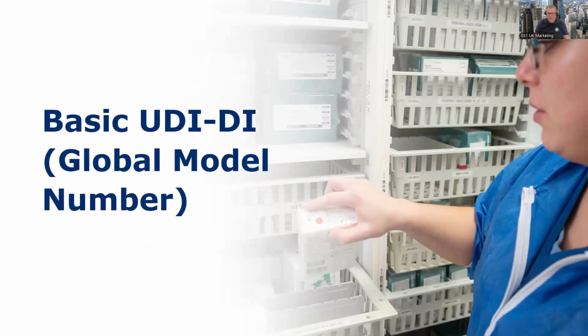So you're here for me to talk about the basic UDI-DI, which, as I said at the beginning of the call, is met. The requirement for that is met using the GS1 Global Model Number. In the same way as the requirement for the unique device identifier, the UDI-DI. The UDI-DI is met by the GTIN using GS1 standards. The basic UDI-DI is met by the GMN, the Global Model Number.